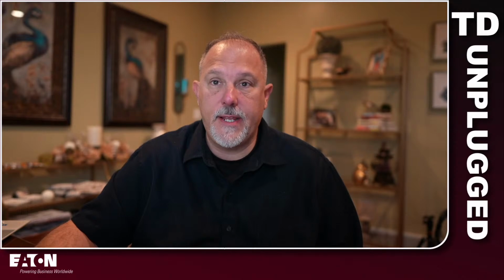230.31 size and ampacity. 230.31(A) probably should just go away. I mean, all conductors need to have an ampacity not less than the calculated load. And maybe it's just because this is the only place we don't have a general requirement. In 230, in part 1, general requirements, we should just basically say all conductors have to have a minimum ampacity to carry the calculated load. And we calculate load in Article 120 now. Well, it was 220, now it's 120. In any case, we have a method in the code to calculate the load currents. But we don't have anything in the general requirements that speaks to it.